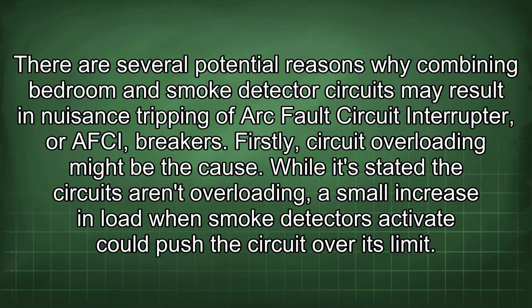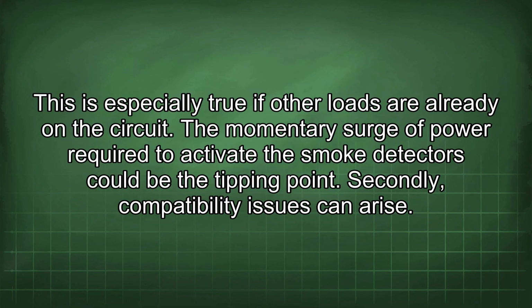There are several potential reasons why combining bedroom and smoke detector circuits may result in nuisance tripping of arc fault circuit interrupter, or AFCI breakers. Firstly, circuit overloading might be the cause. While it's stated the circuits aren't overloading, a small increase in load when smoke detectors activate could push the circuit over its limit. This is especially true if other loads are already on the circuit. The momentary surge of power required to activate the smoke detectors could be the tipping point.